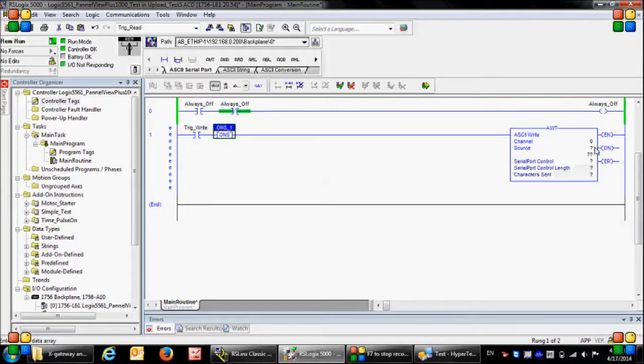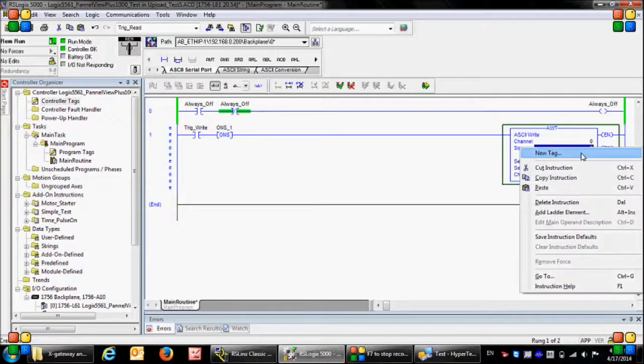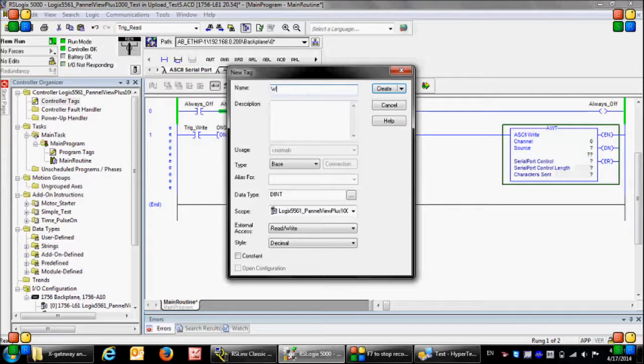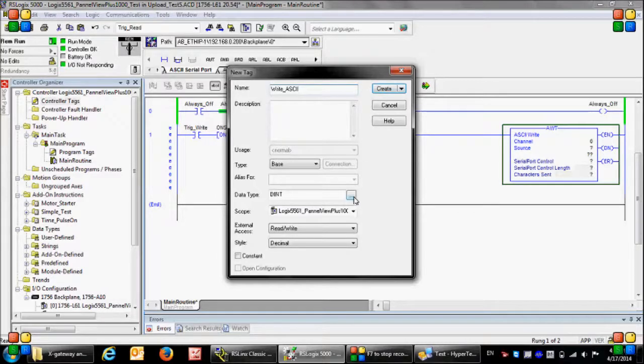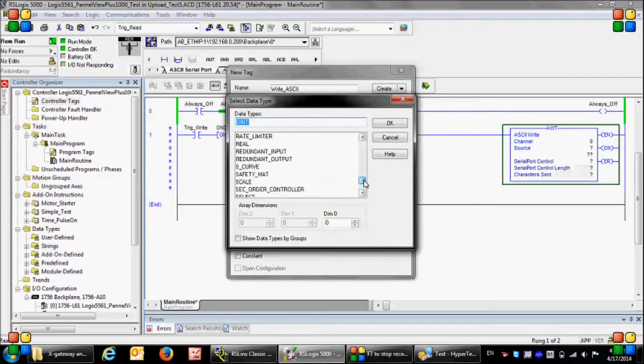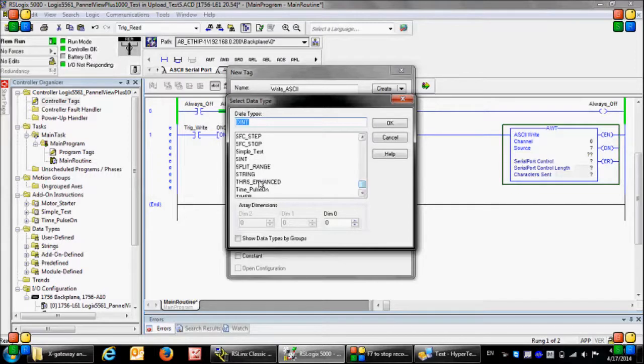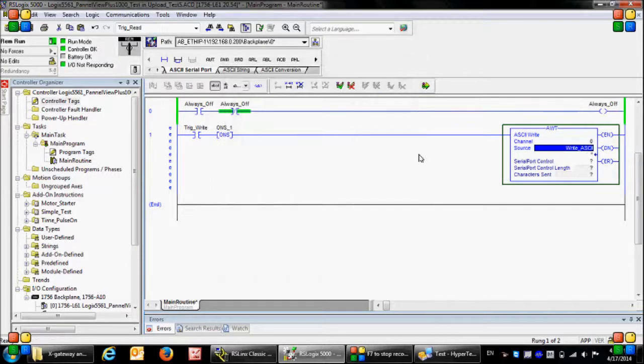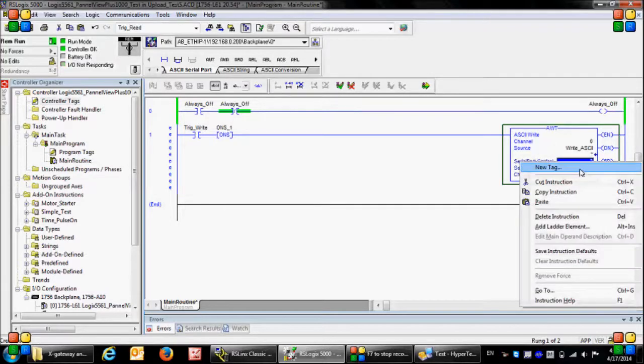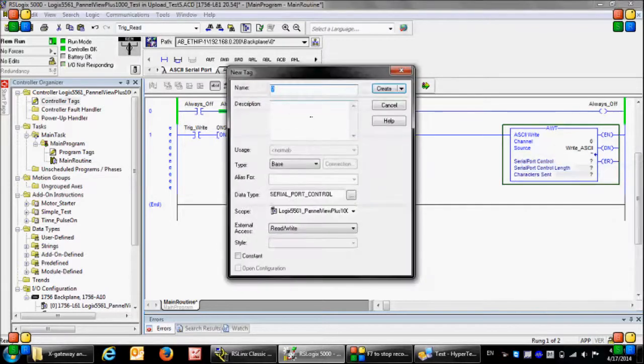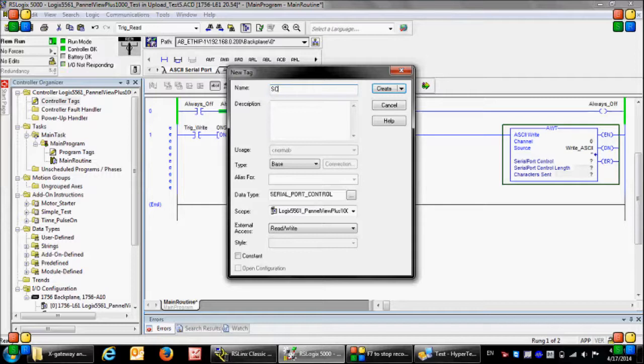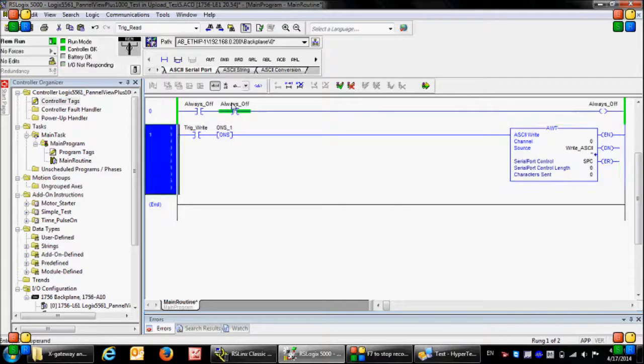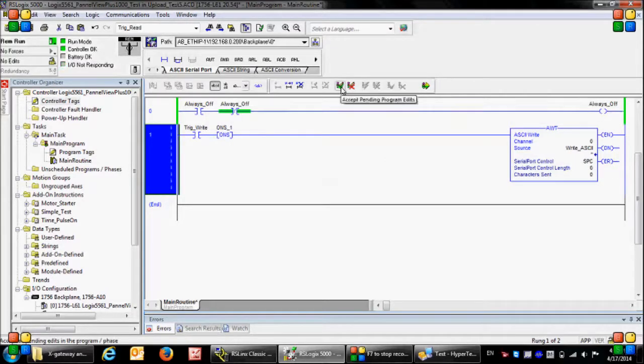And for the ASCII write instruction, in the channel number zero, for the source a variable of type string in which I will write my desired message. So here I need to change the type to string, and I need to assign a new tag of type serial port control. Now let's download this new rung to the PLC.